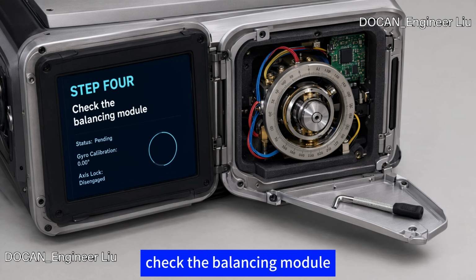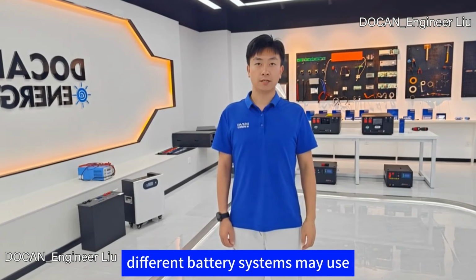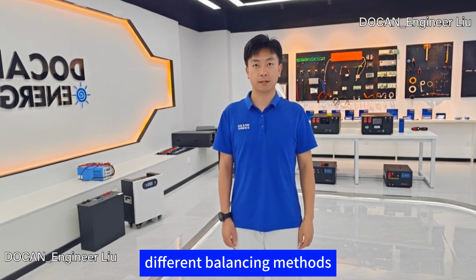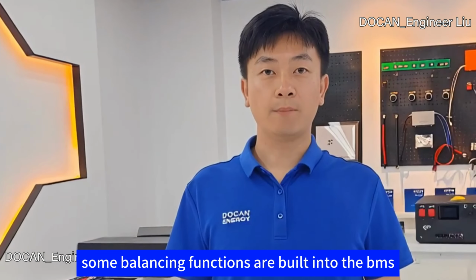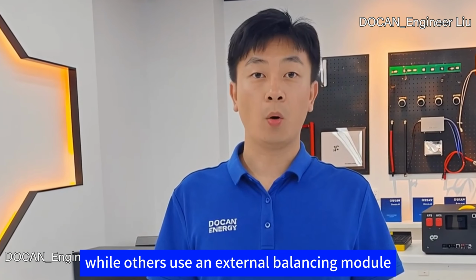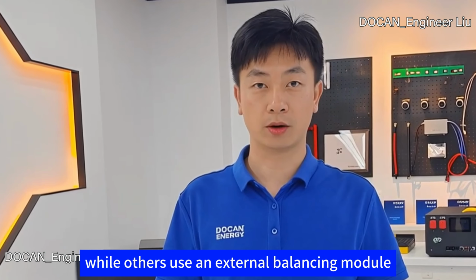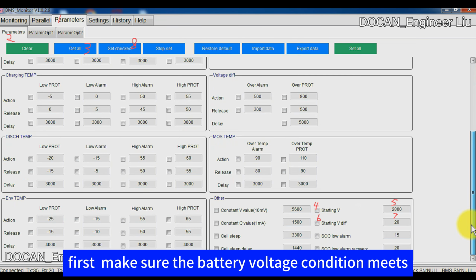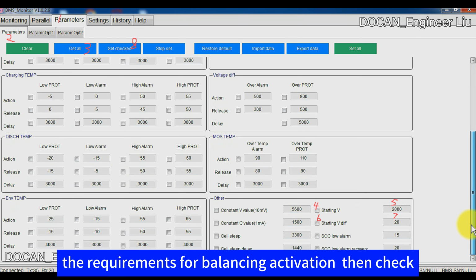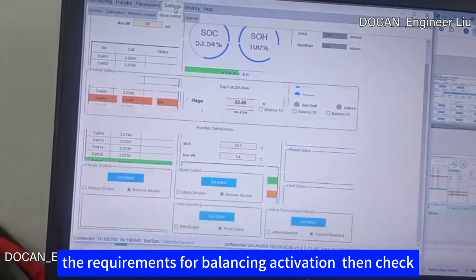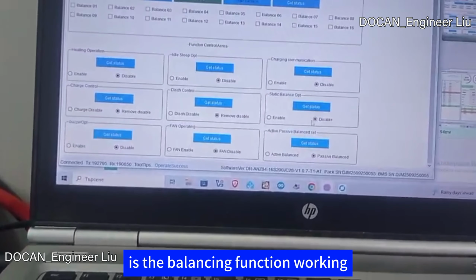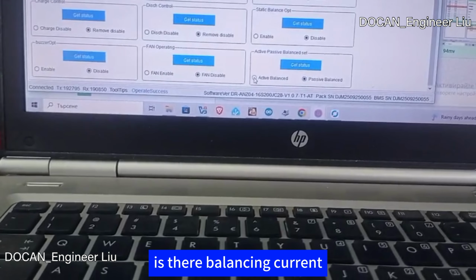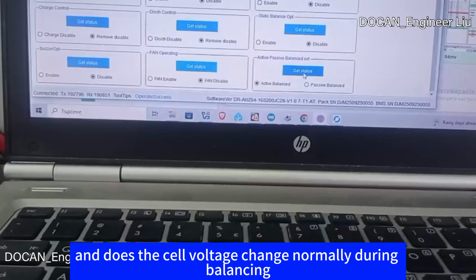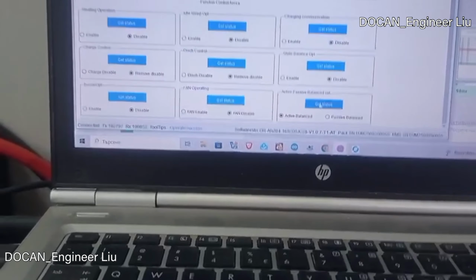Step 4. Check the balancing module. Different battery systems may use different balancing methods. Some balancing functions are built into the BMS, while others use an external balancing module. First, make sure the battery voltage condition meets the requirements for balancing activation. Then check, is the balancing function working? Is there balancing current? And does the cell voltage change normally during balancing?